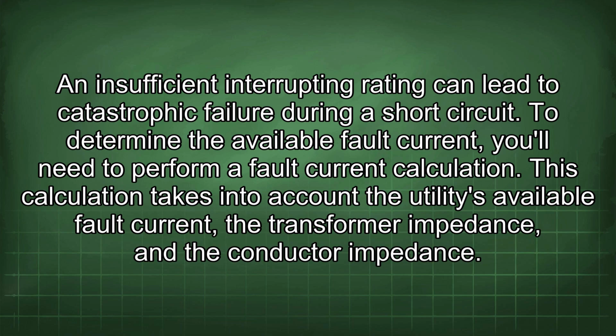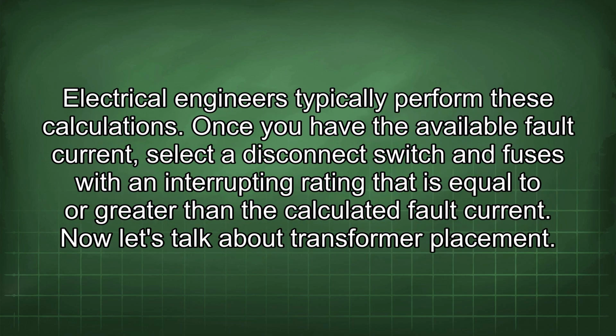To determine the available fault current, you'll need to perform a fault current calculation. This calculation takes into account the utility's available fault current, the transformer impedance, and the conductor impedance. Electrical engineers typically perform these calculations. Once you have the available fault current, select a disconnect switch and fuses with an interrupting rating that is equal to or greater than the calculated fault current.